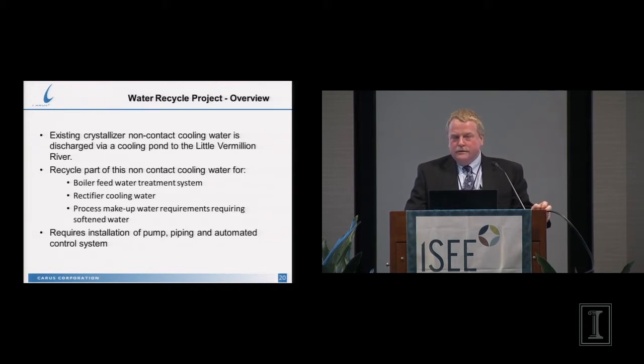We use some of this water for rectifier cooling. Even though it's 20 degrees warmer, it didn't affect our requirement for rectifier cooling, so now that water is free. And then we use it for makeup water in the pump, in the plant.